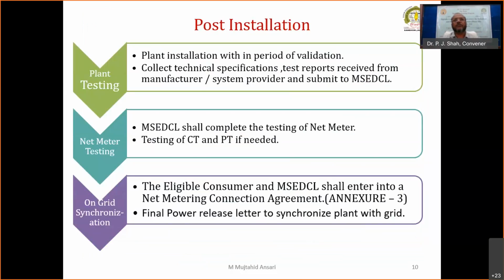Now, post installation: once the installation is completed, you have to get the first permission from MSEDCL. Now we will go for the post-installation stages. The first is plant testing. Once you have connected the inverters, ACDBs, DCDBs and earthings, we are going to conduct some small tests, but we have to take care that we cannot inject power into the system because we have not got the release letter. So these are only in-plant testings, during the period of validation, where we collect the technical specification testing reports received from the manufacturer. These are the test reports of the PV modules, inverters, lightning arresters and all the other testing reports.